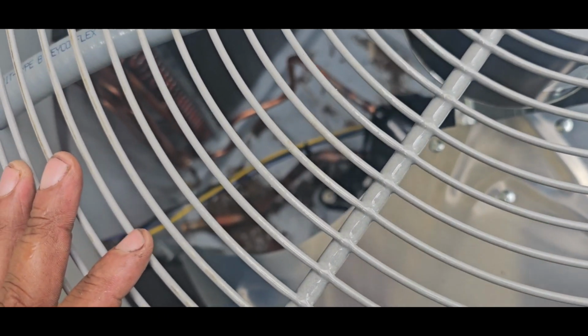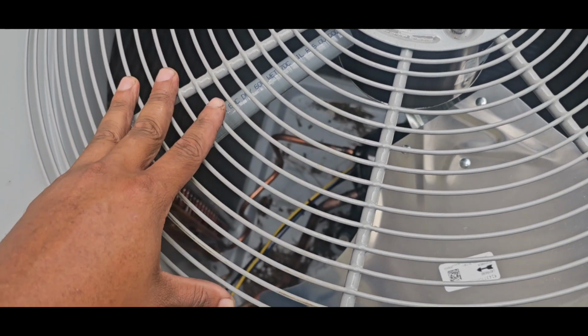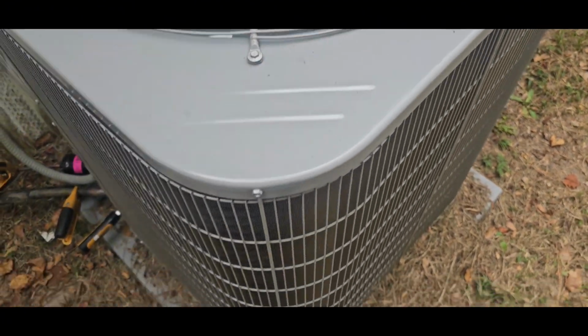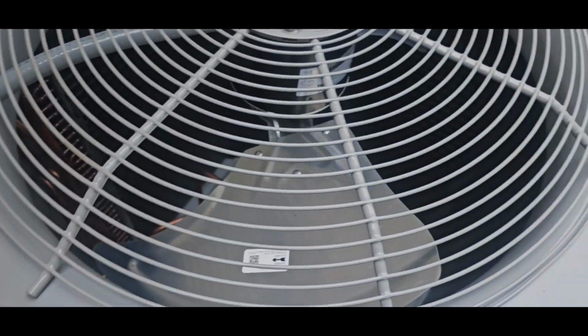Of course, the camera's being retarded. There's no pressure switches in here. This is such an entry-level model unit. There's no pressure switches, not a high or a low. The only wires going in here are for this motor and for the compressor.